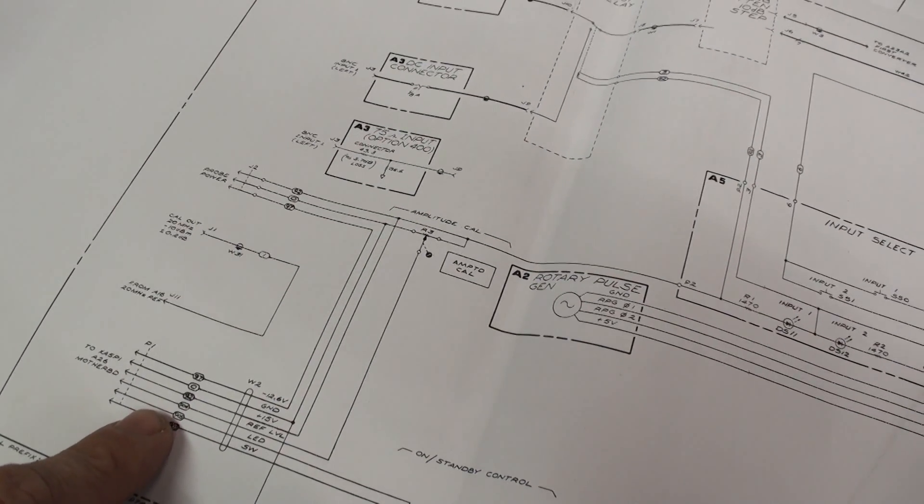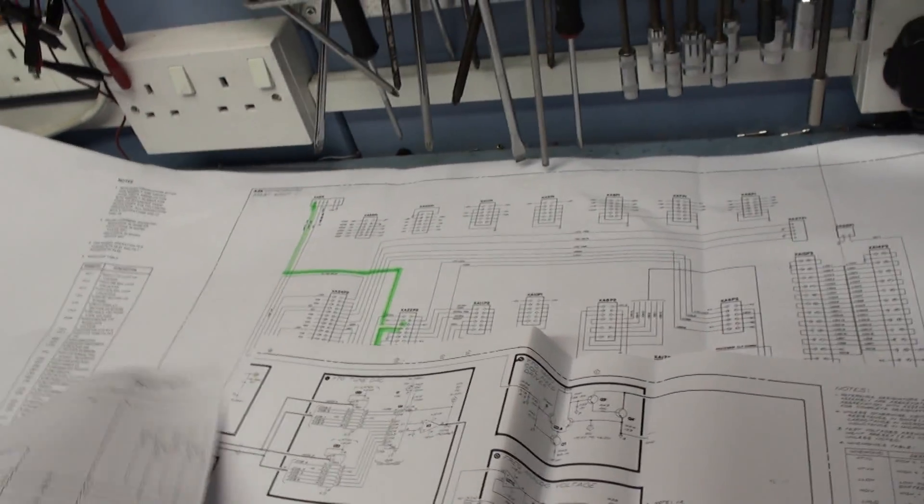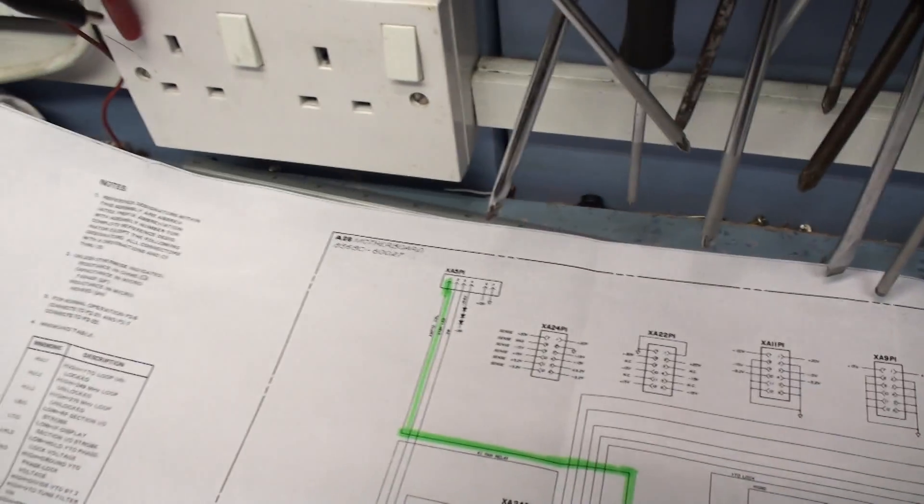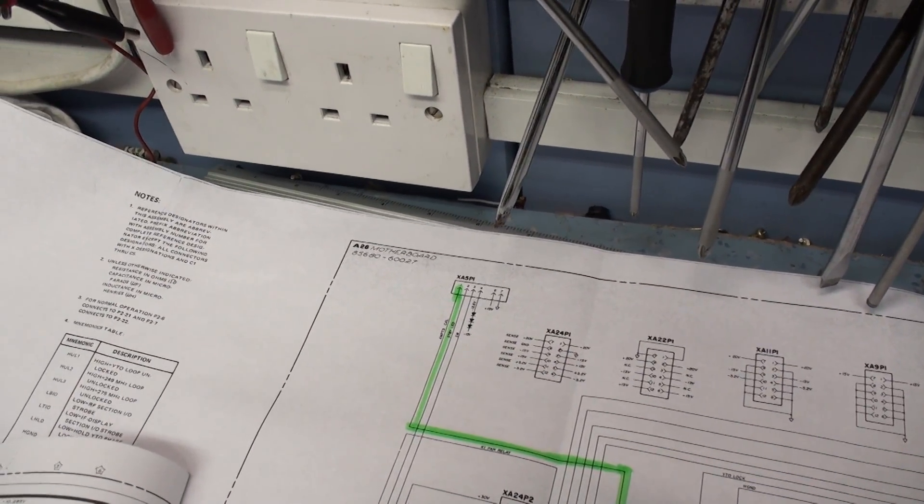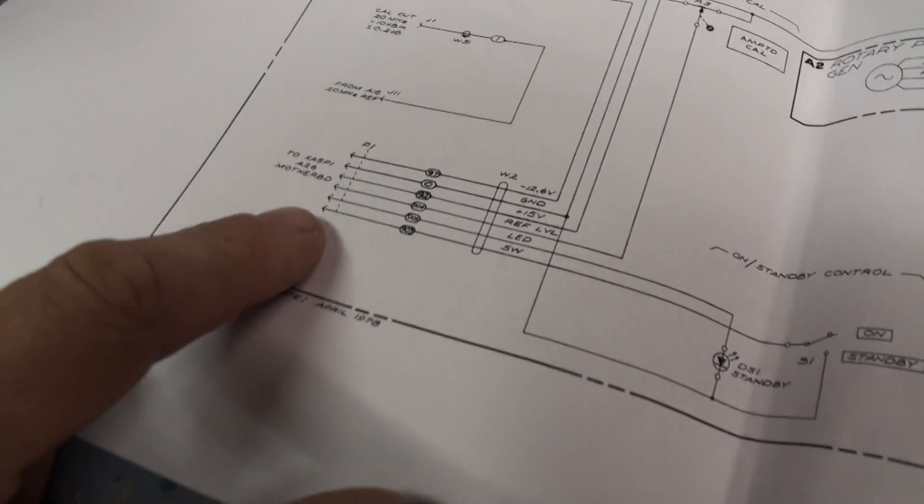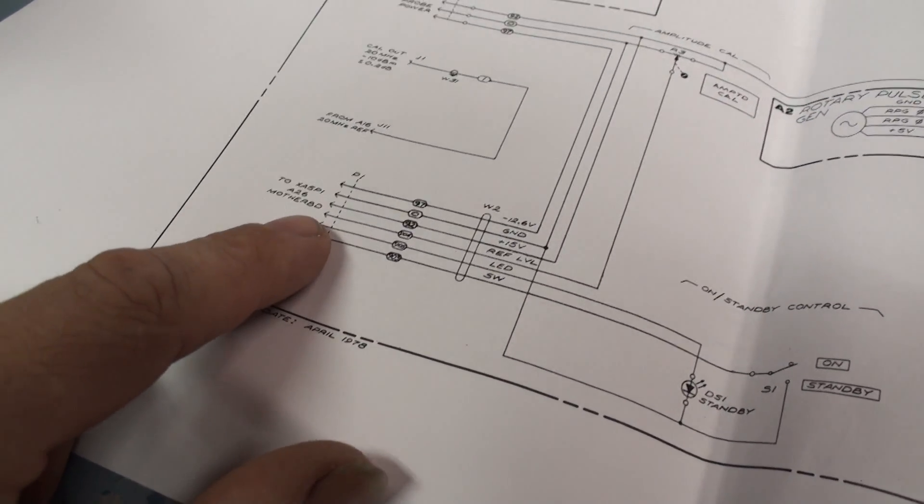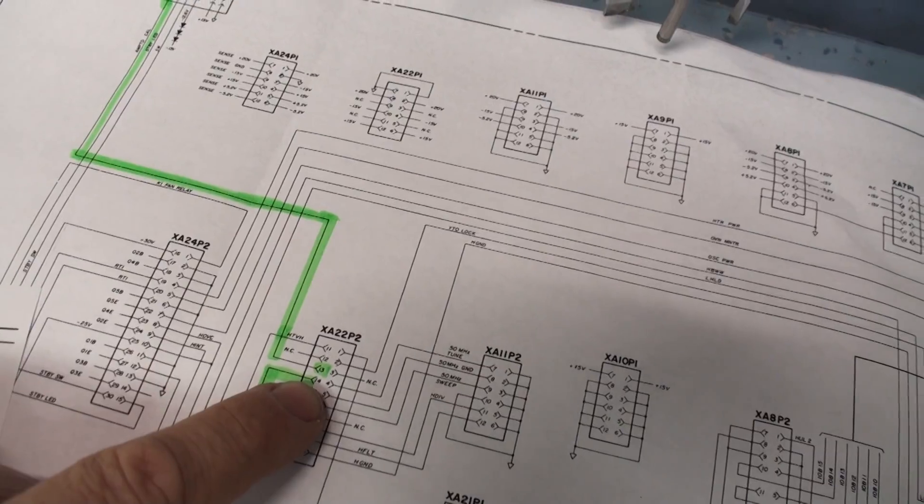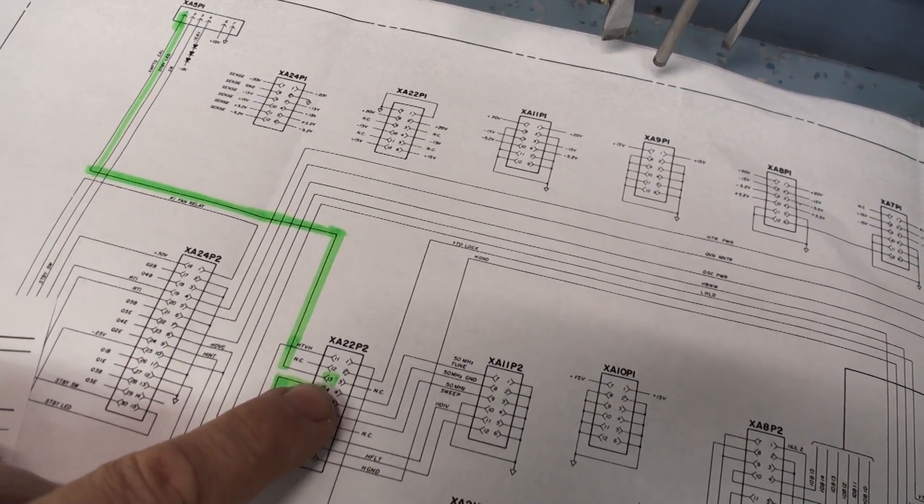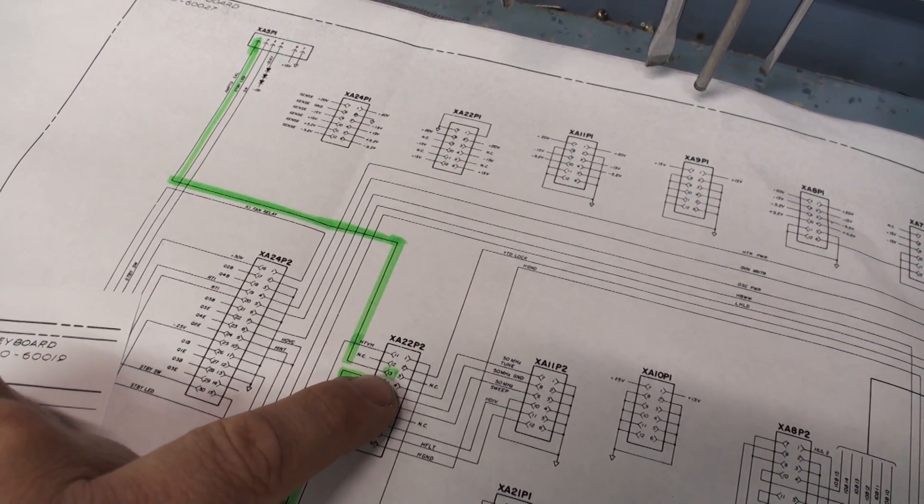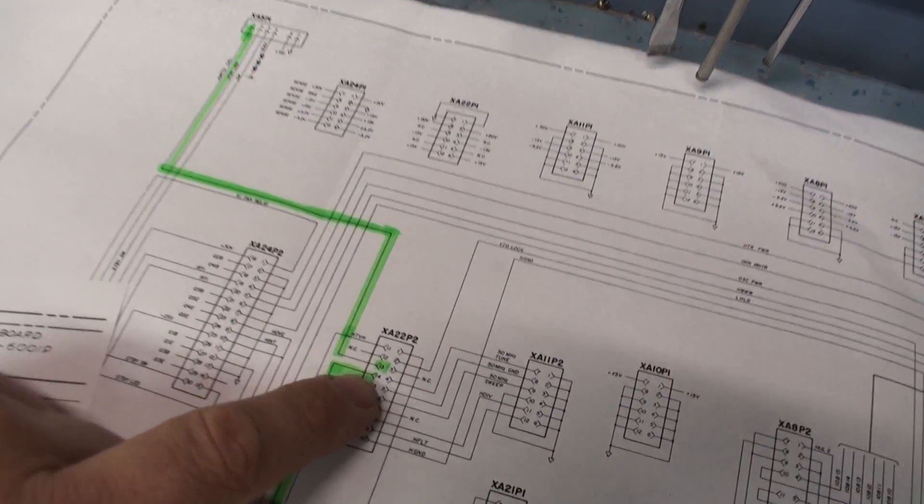Now, follow it through on the motherboard circuit diagram, which is this big circuit here. I printed all these out from the manual, so it means I can highlight them and things. This is the connector you see on the front panel. It leaves the front panel and goes to this connection here. The XA5P1, the A26 board, which is the A26 is the motherboard. There it goes there. And it comes through here, down. And it's first board of call is board 22, P2. Now what that means is, it'll be the A22 board, and it'll be on the plug 2.